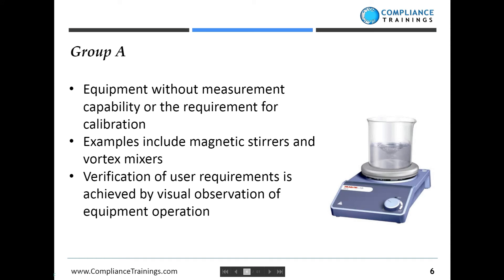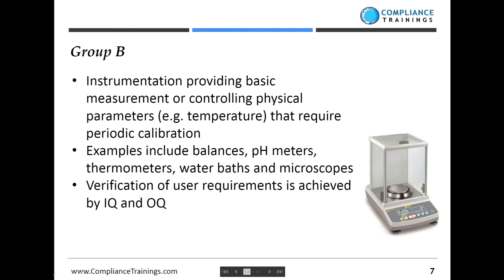Instruments in group A are the simplest laboratory instruments — things like magnetic stirrers and vortex mixers. Generally all we're required to do to qualify these is to check visually that they do what they're intended to do. For group B instruments we add a little bit of complexity. These are instruments designed to measure something, and they will require periodic calibration. For these relatively simple measurement instruments we would perform installation and operational qualification.